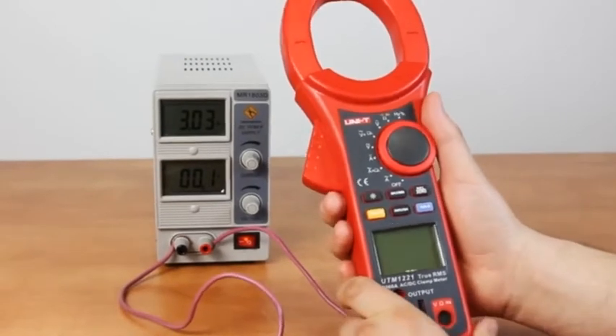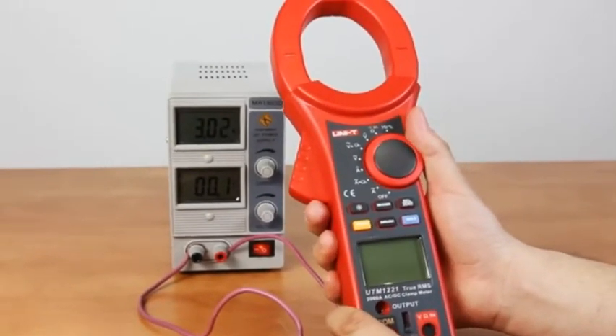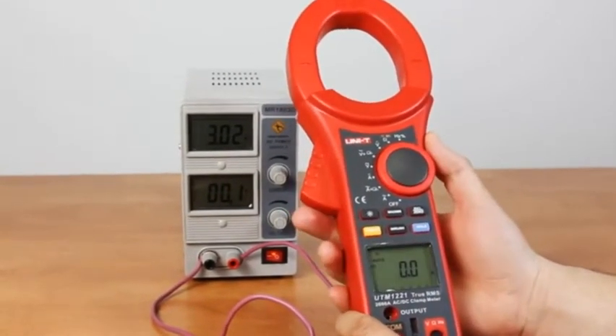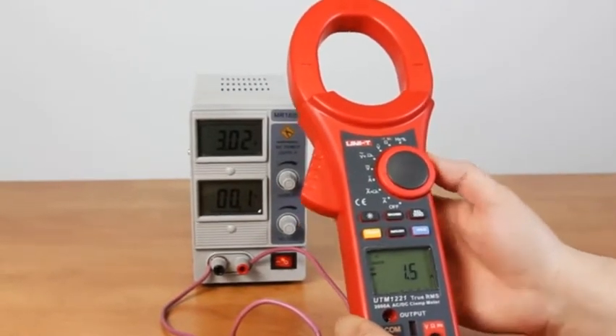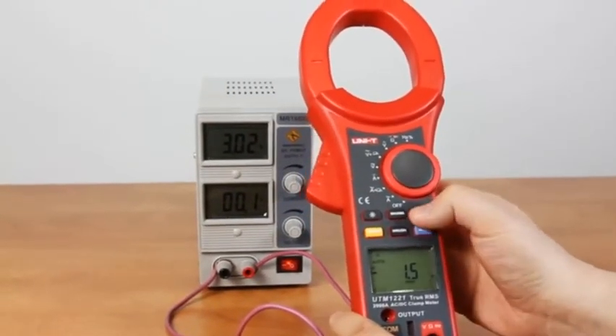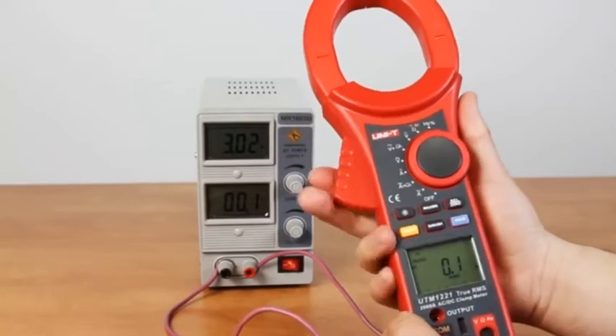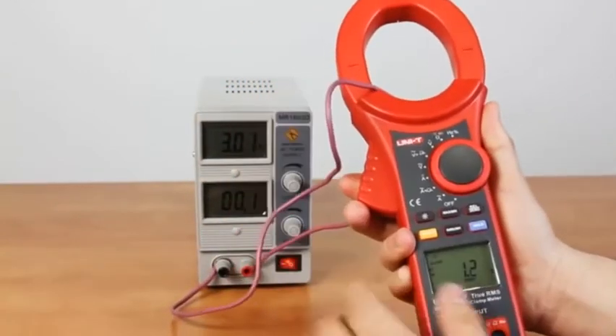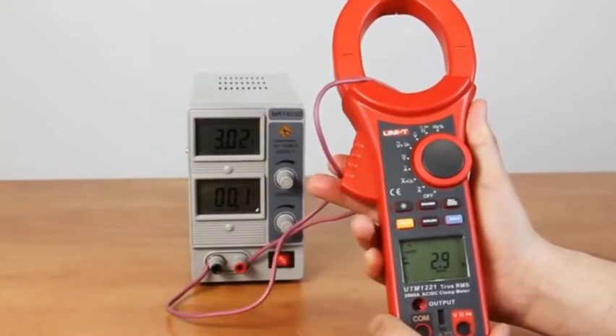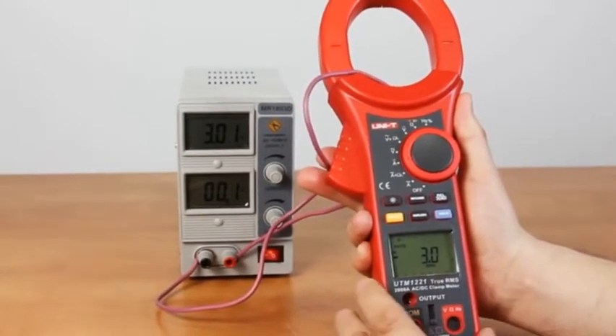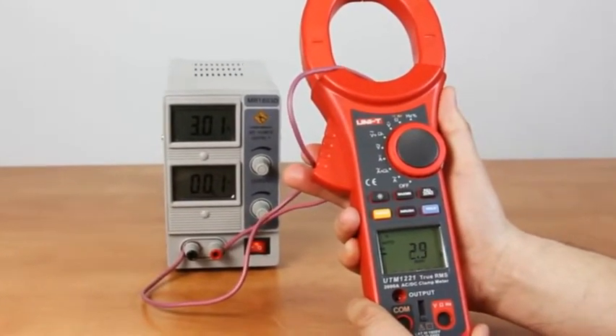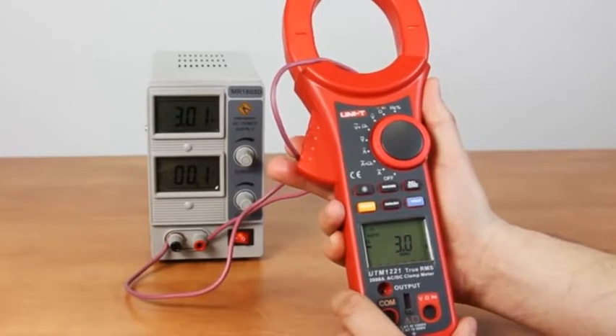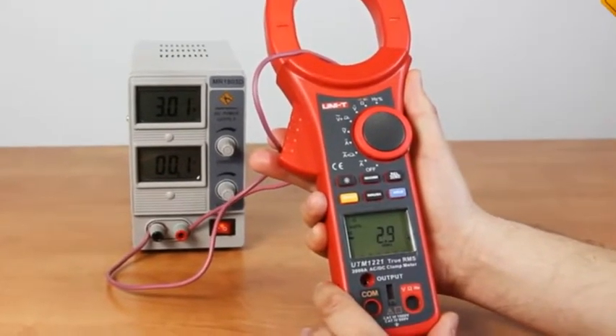Now let's measure DC current. Turn on the meter and switch to DC current measurement. Before starting the measurements, press the zero button to reset the display readings to zero. Start the measuring process. We may see a slight inaccuracy in the last order. Taking into account the DC current measuring range of 2000 Ampere, we consider the result excellent.